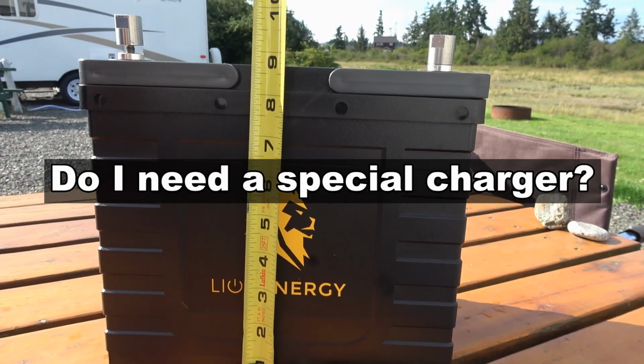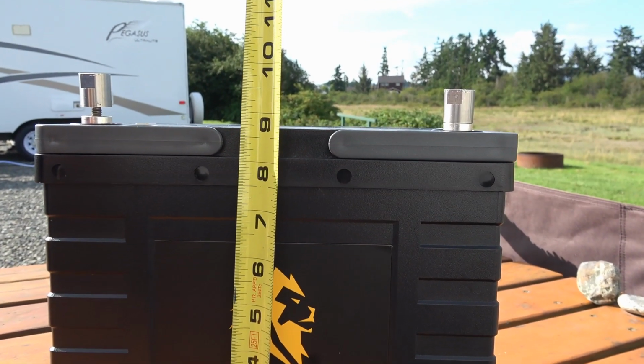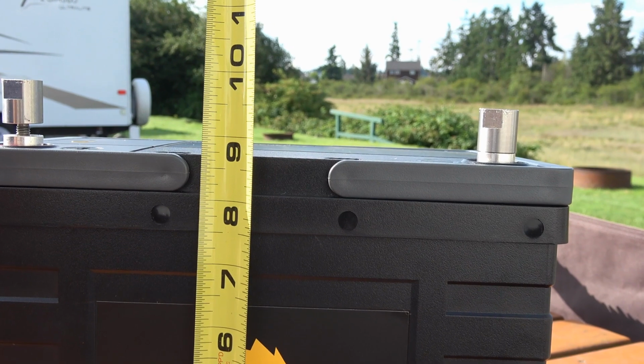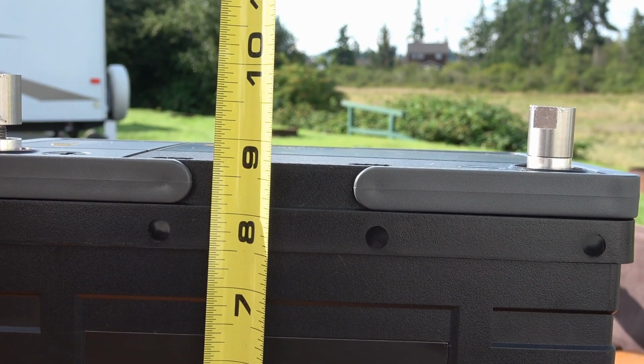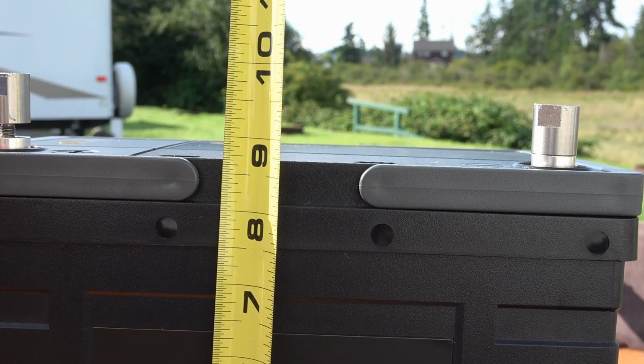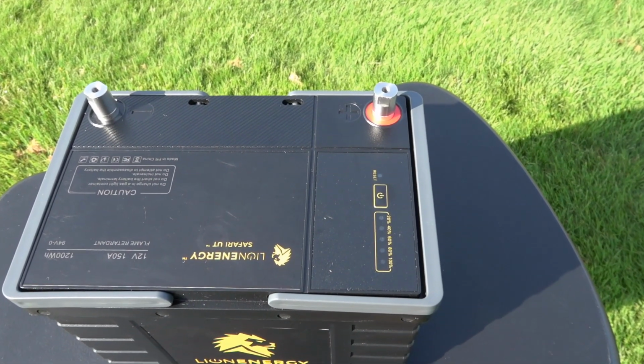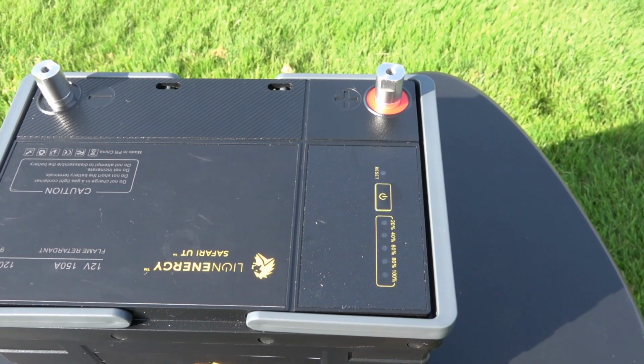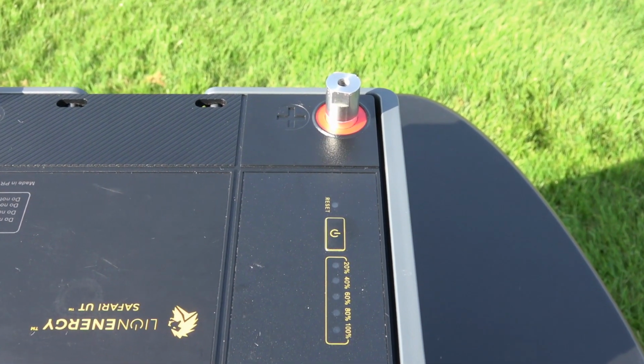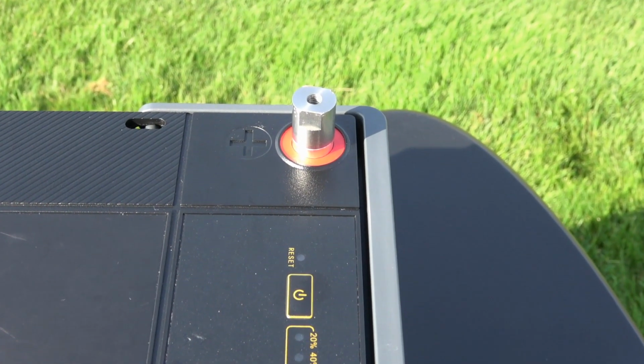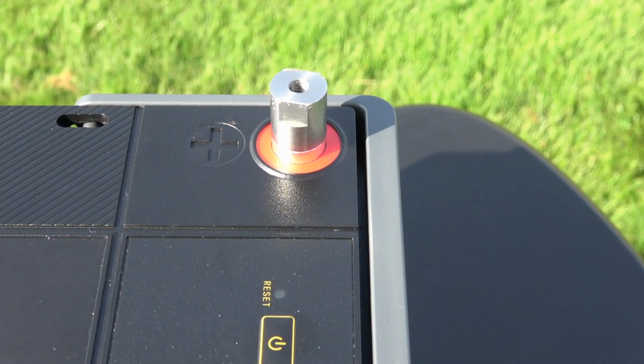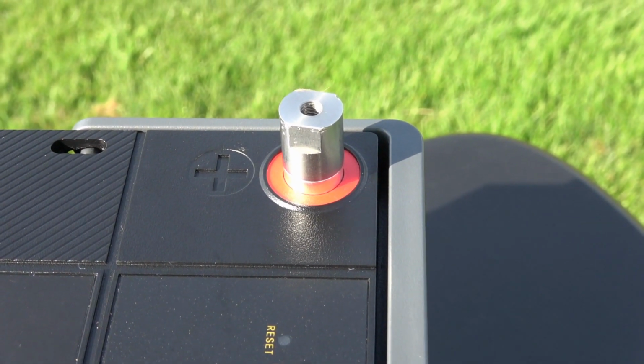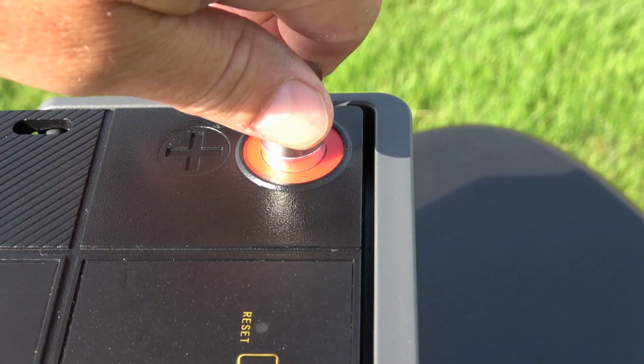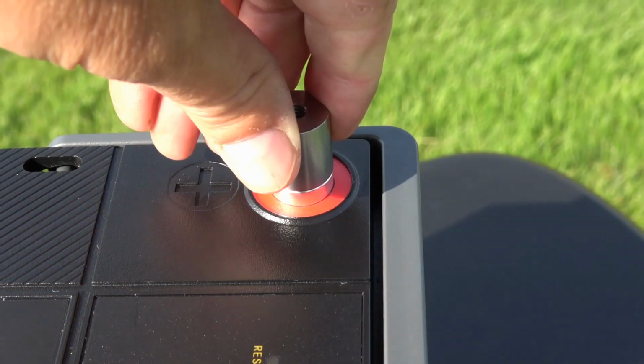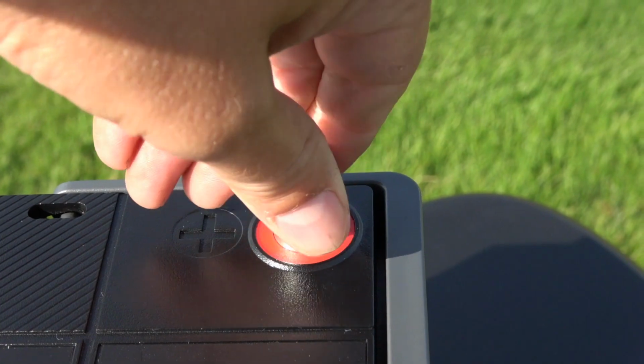Do you have to buy special chargers? Many modern inverter chargers, hybrid type chargers, and solar charge controllers can be optimized for lithium batteries simply by adjusting their charging voltage settings. Some already have built-in lithium charge profiles, making the task dead simple - a lot of times you just go into their setup screen, change a few settings, and bang, it's ready to go. Because of the sophisticated BMS inside the Safari UT batteries from Lion, they can be charged by most existing OEM lead acid charge converters, with the caveat that using a lithium-specific charge converter will reduce the charge times and maximize the battery's usable energy and life.